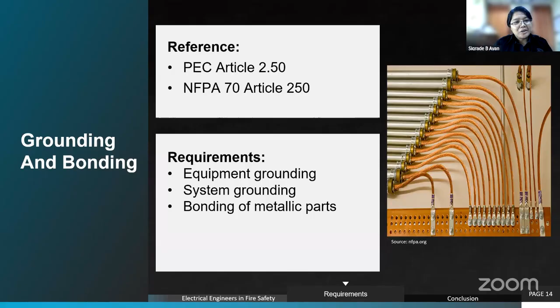First, our electrical plans must show the load calculations, which cover your demand factors and load classifications, while your single line diagram will show your transformer and panel hierarchy, sources, and protective devices. Your protection system, which ensures fault interruption, should show overcurrent protection and short circuit protection, while your grounding details in the electrical plans should present the grounding electrode system, equipment grounding, and bonding details. From this, we'll be able to see that our plans or design is compliant by evidence.